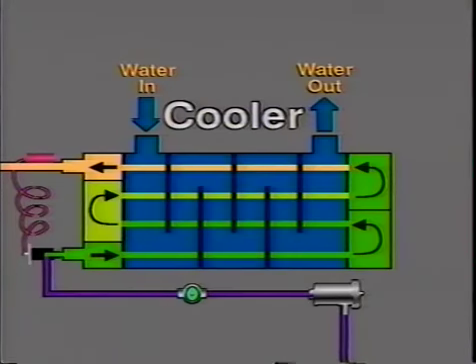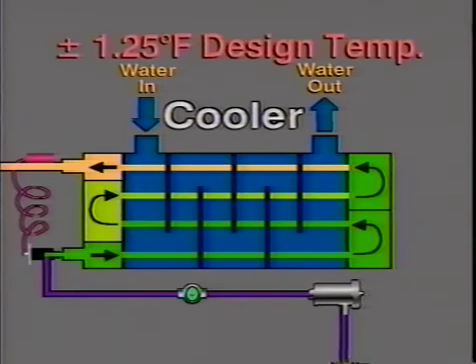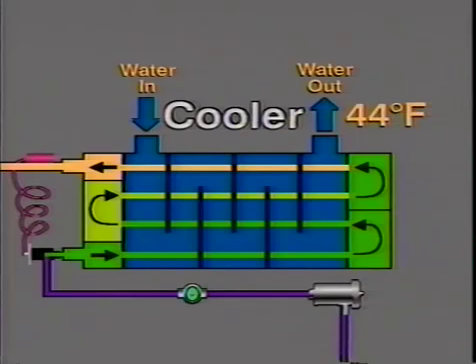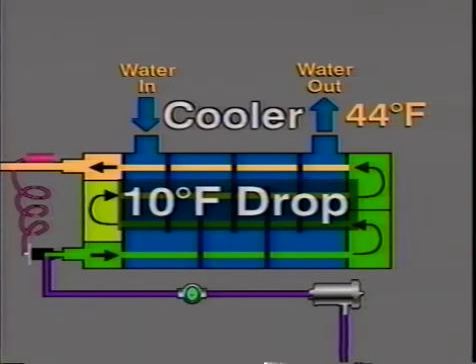Now, let's look at symptoms of some common problems. After a chiller has pulled the building load down to design conditions, it should keep the cooler's leaving chilled water temperature within plus or minus 1.25 degrees Fahrenheit of the design temperature. Let's say our design leaving chilled water temperature is 44 degrees, and at full load conditions, there is a 10-degree drop through the cooler. Now that means our entering chilled water will be at 54 degrees.